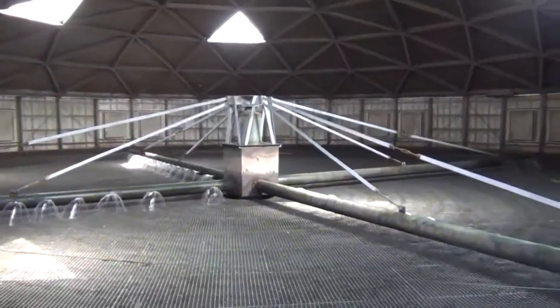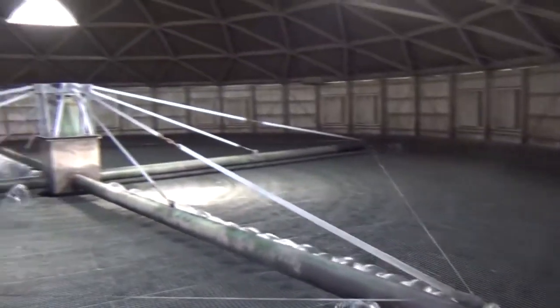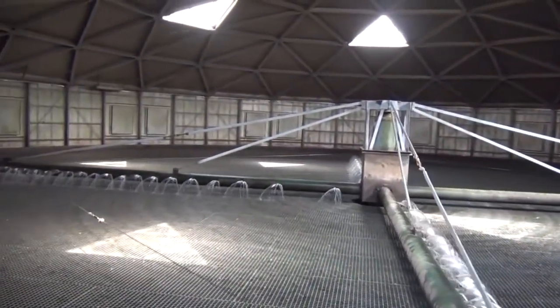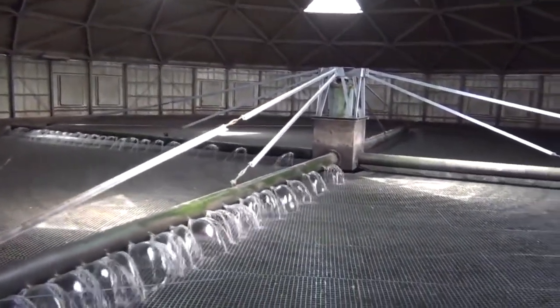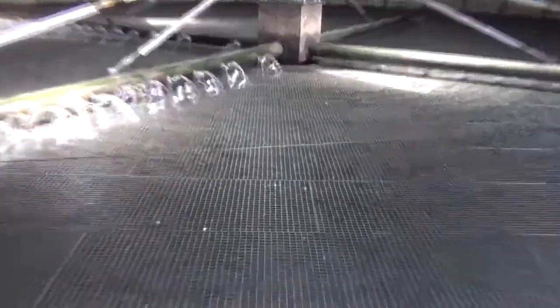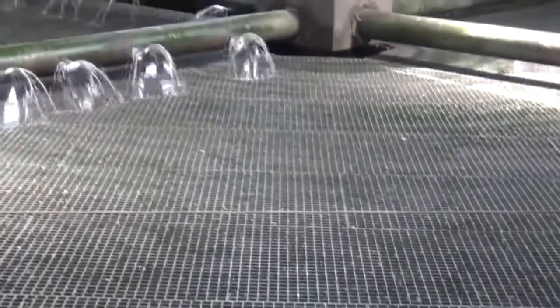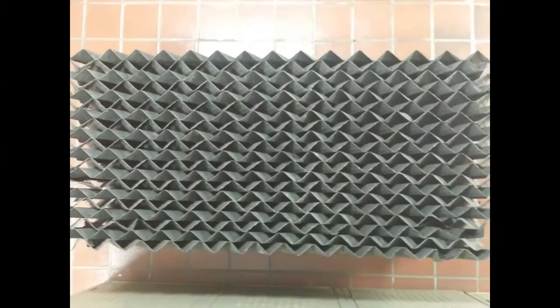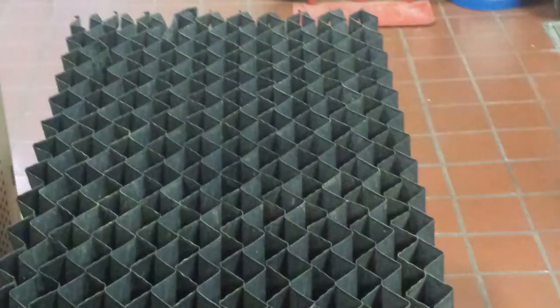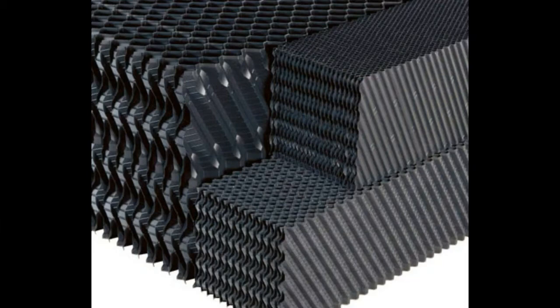The next step is biological treatment, known as the secondary treatment process. Wastewater pumped from the primary effluent wet well is spread evenly across the surface of the two trickling filters through revolving pipes known as distribution arms, which have holes called ports. The trickling filters are 86 feet in diameter and about 46 feet tall — visible from Route 1 between Cook's Corner and Main Street. The biological treatment process happens when microbes consume organic matter in the wastewater and convert it to carbon dioxide, water, and energy for their own growth. The microbes grow on a plastic cross-flow media that looks like a honeycomb. The media in each filter is 22 feet deep, and the cross-flow design increases surface area. The surface area in each filter is 3,830,000 square feet — the equivalent of 80 football fields. More area means more room for microbes to grow.